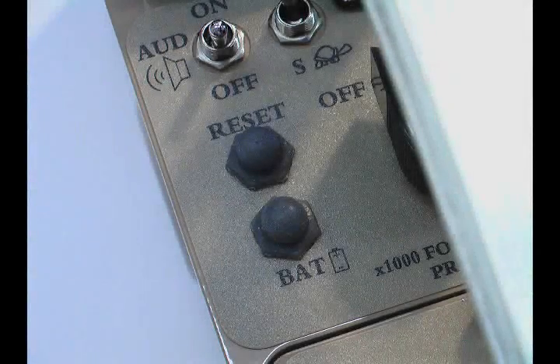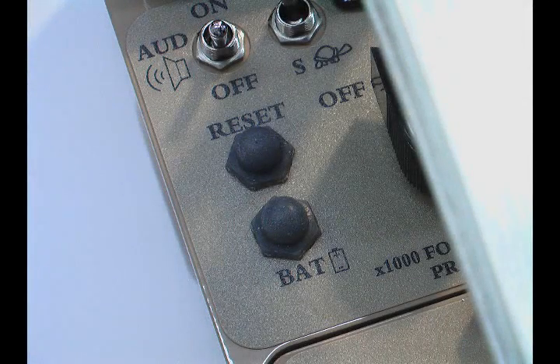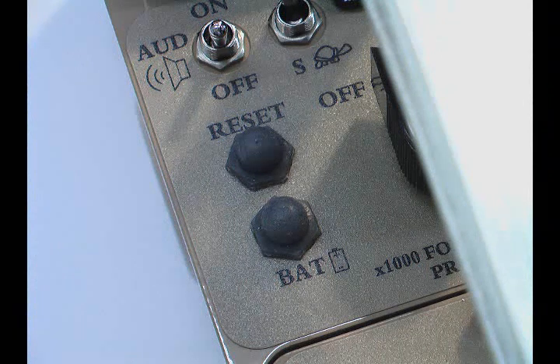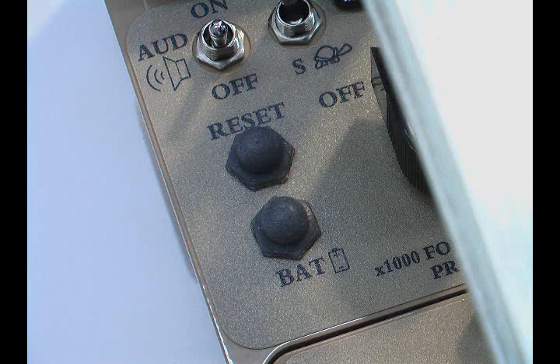The fast-slow toggle switch changes the meter response time of the instrument from fast to slow. In the F position, there is a fast response and a large deviation. In the S position, there is a slow response and less deviation. The reset button, when depressed, provides a rapid means to drive the meter back to zero. The battery check button, when depressed, provides a visual means of checking the battery charge status. The instrument must be turned on to do this check.